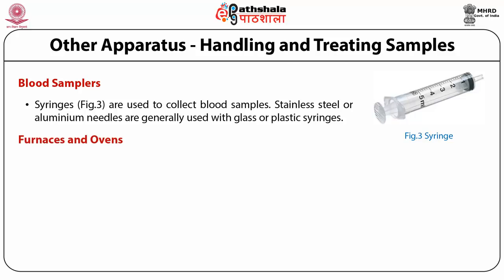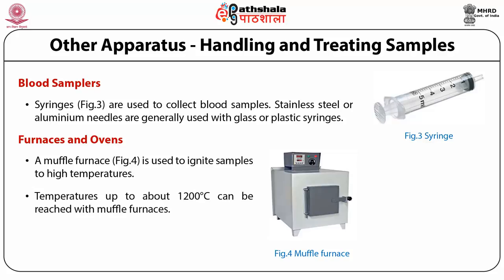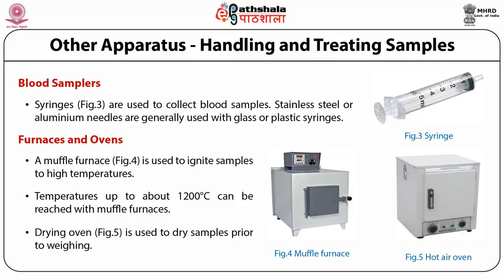A muffle furnace is used to ignite samples to high temperatures, either to convert precipitates to a weighable form or to burn organic materials prior to inorganic analysis. There should be some means of regulating temperature, since losses of some metals may occur at temperatures in excess of 500 degrees centigrade. Temperatures up to about 1200 degrees centigrade can be reached with muffle furnaces. A drying oven is used to dry samples prior to weighing. These ovens are well ventilated for uniform heating; the usual temperature employed is about 110 degrees centigrade, but temperatures of 200 to 300 degrees centigrade may be obtained.